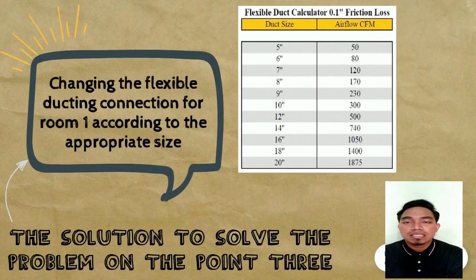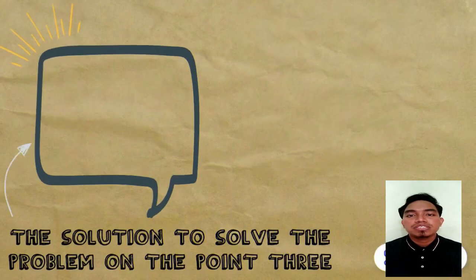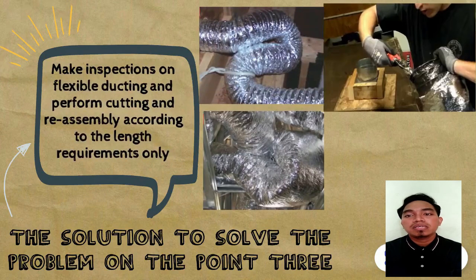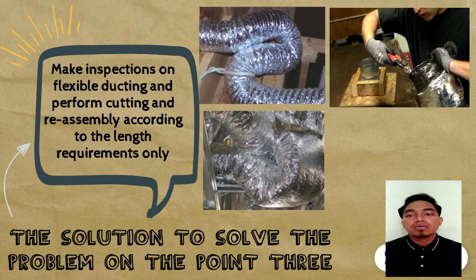The solution to solve the problem in point 3 is we need to do maintenance on the ducting system by changing the flexible ducting connection for room 1 to the appropriate size if there is a difference in size compared with the flexible ducting of room 2 and room 3. Next, inspect the flexible ducting and perform cutting and assembly according to the length requirement only.